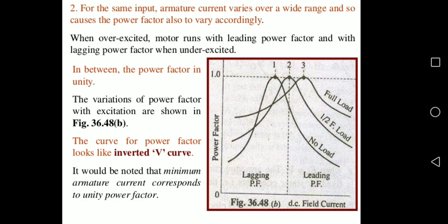That means when running with lagging power factor, the machine is underexcited; if excitation is increased to 100%, that is unity condition; and if it is increased more than 100%, the machine is operating at an overexcited condition.